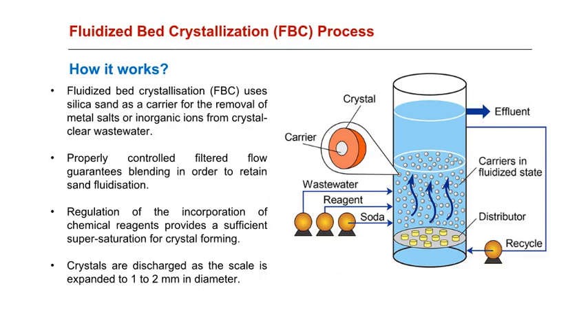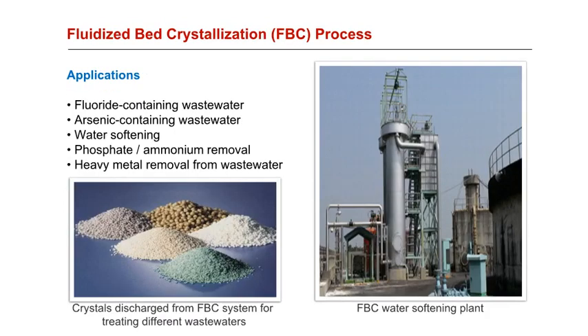Fluidized bed crystallization, or FBC, uses silica sand as a carrier for the removal of metal salts or inorganic ions from crystal clear wastewater. Properly controlled filtered flow guarantees blending in order to retain sand fluidization. Regulation of the incorporation of chemical reagents provides sufficient supersaturation for crystal forming; crystals are discharged as the scale is expanded to 1–2 mm in diameter. Examples of FBC applications include fluoride-containing wastewater, arsenic-containing wastewater, water softening, phosphate and ammonium removal, and heavy metal removal from wastewater.